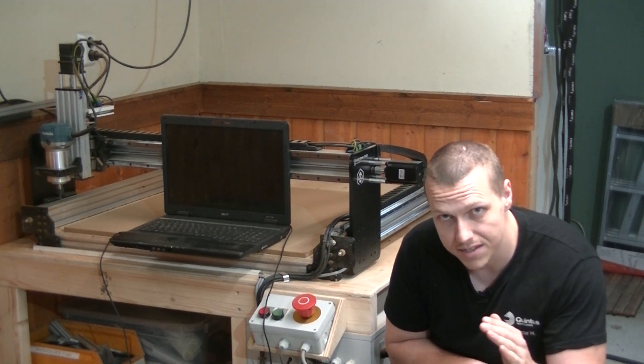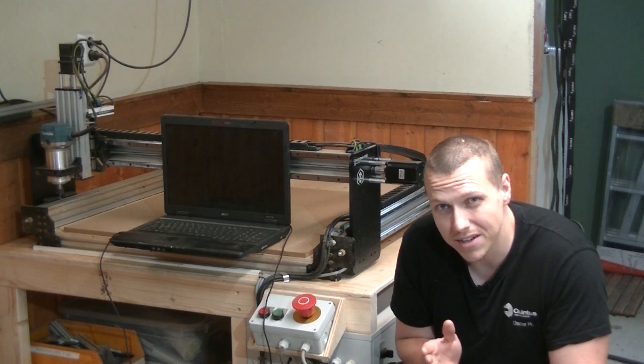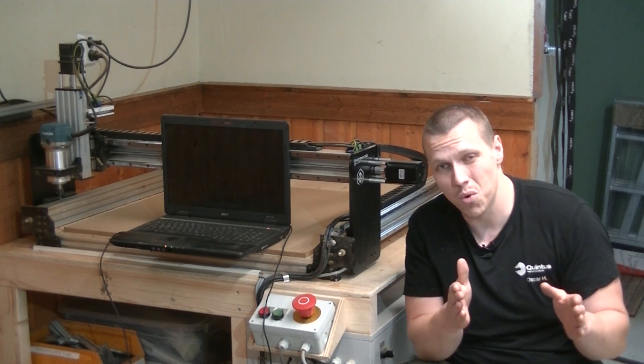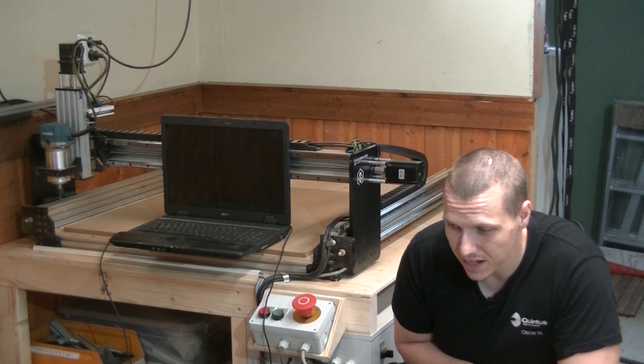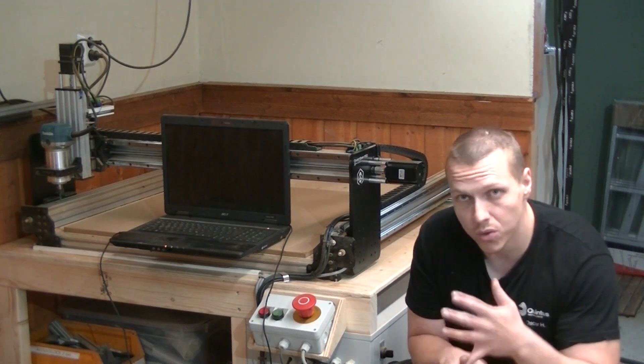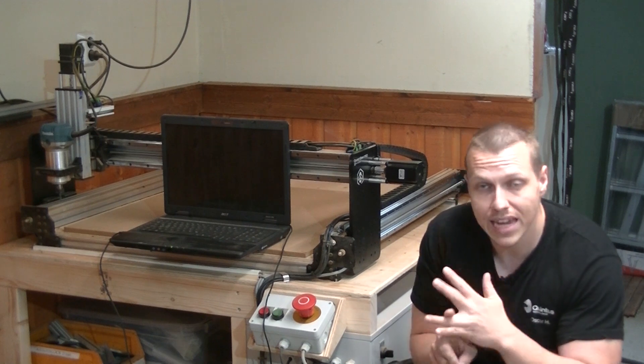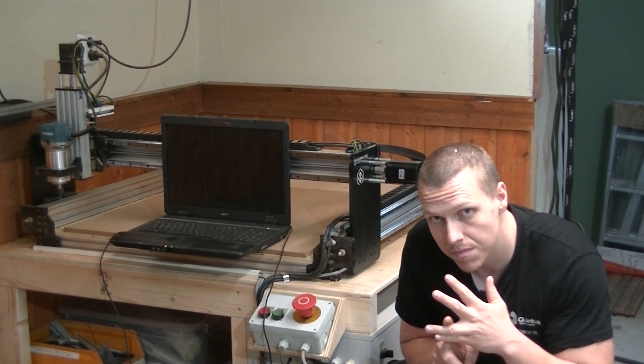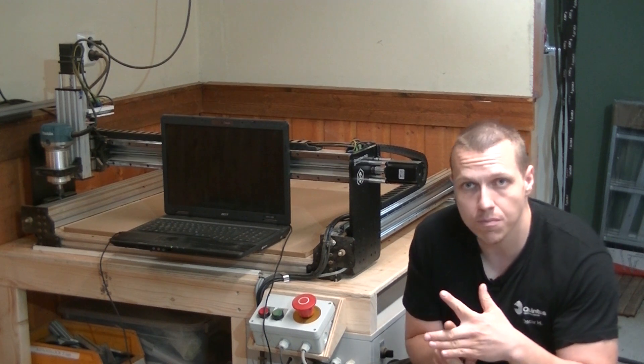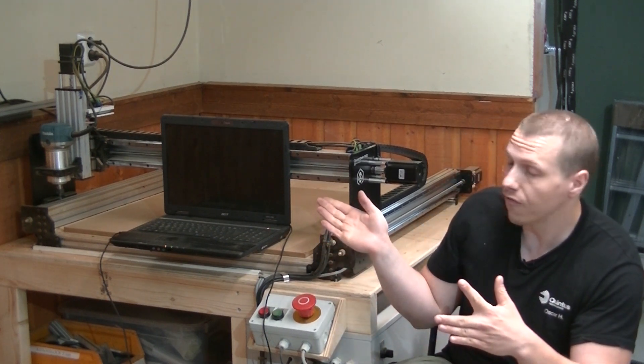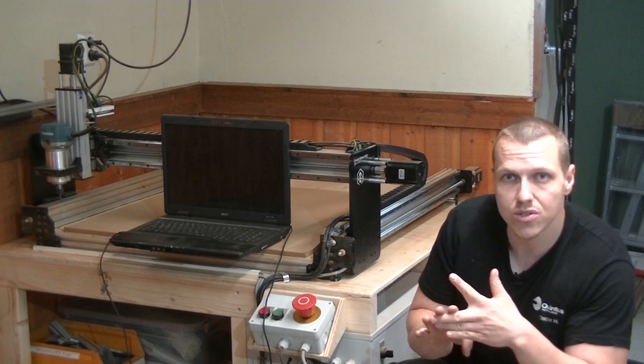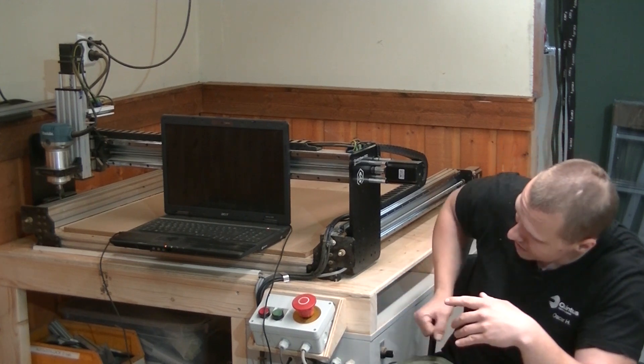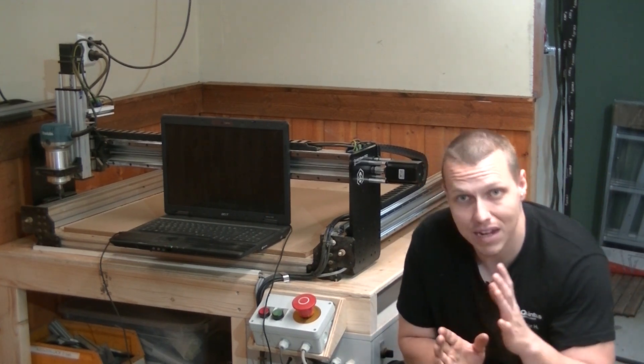So if you're choosing between two sizes of electrical cabinet and you think you could fit everything in the smaller one, get the bigger one anyway. This will improve everything—you'll both have better air circulation for cooling, you'll have a lot easier time laying out all the cables and installing all the components, and you'll have space to grow over time. If you want to add components, let's say a fourth axis or something, you'll have space to add all the necessary control components inside the cabinet. So definitely get bigger if you can.